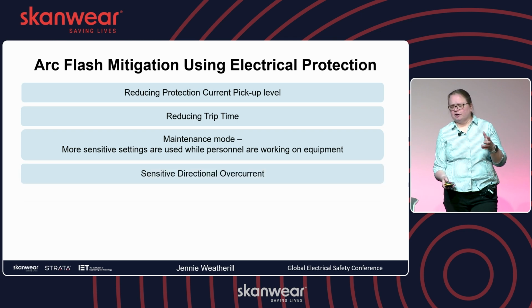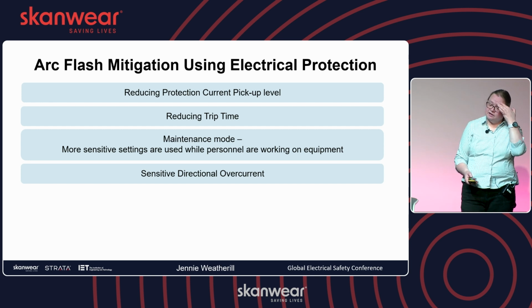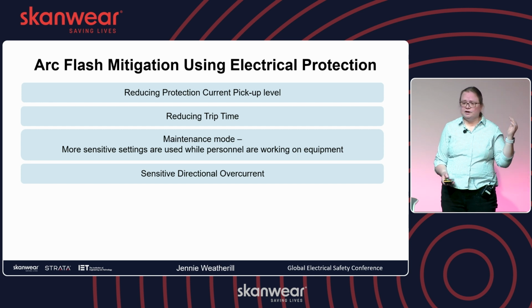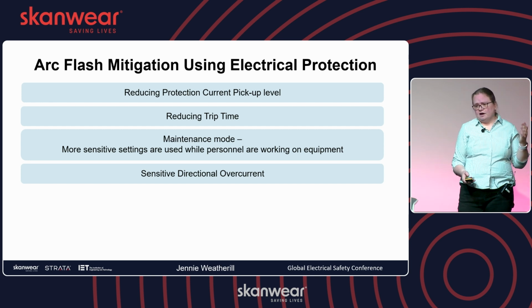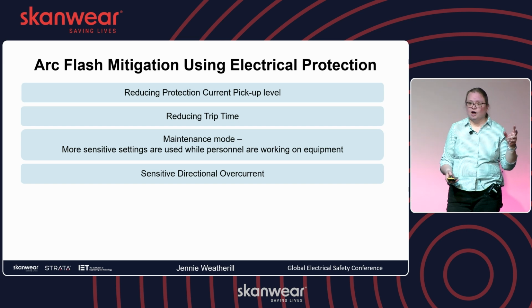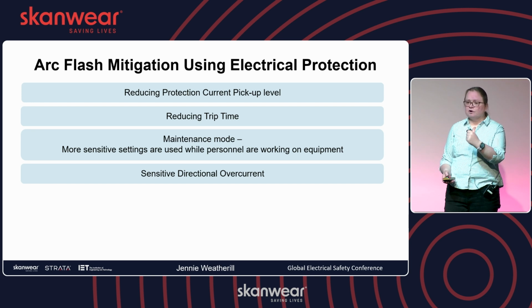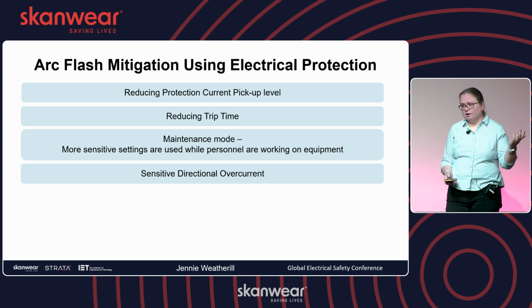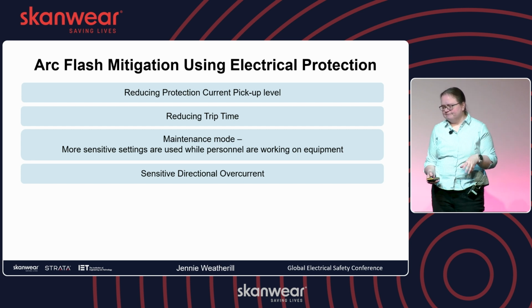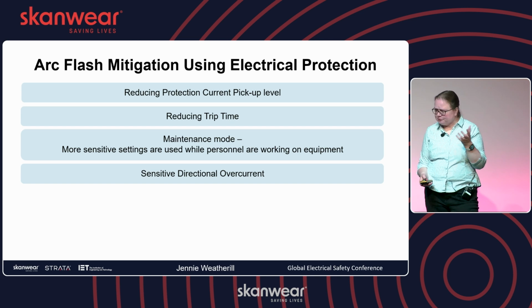Sensitive directional overcurrent, this is one we've used in the wind industry. So when you're on a generation circuit, your highest effective loads when you're generating are going out of the wind farm. But when you have a fault, the fault current tends to flow in. So you can actually set the settings a lot lower than your generation current, because as soon as they're coming in the other direction, you know it's a fault. There are sensitive bits about load encroachment and things that you need to consider, but it's another one to think about.